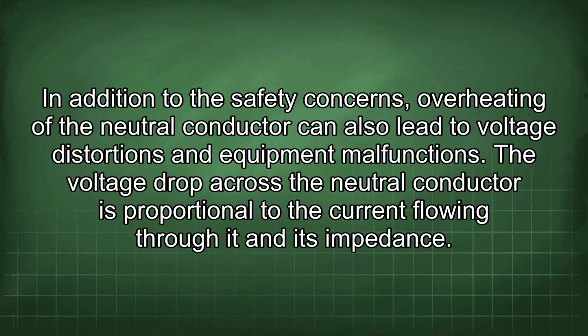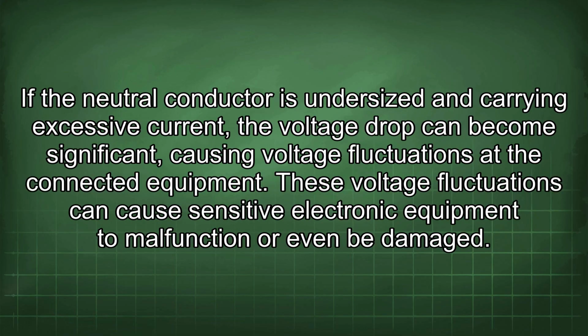The voltage drop across the neutral conductor is proportional to the current flowing through it and its impedance. If the neutral conductor is undersized and carrying excessive current, the voltage drop can become significant, causing voltage fluctuations at the connected equipment. These voltage fluctuations can cause sensitive electronic equipment to malfunction or even be damaged.